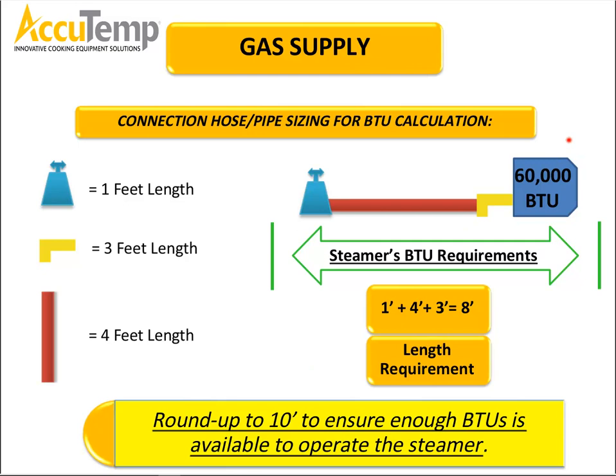Now, one thing to remember is we want to be over by 10%. In other words, if you go bare minimum and say, hey, I can hook this up, and yes, in my calculations I've got exactly 60,000 BTUs running at this connection, nope, add 10% to that. I want to see that connection be able to support 70,000 or 66,000 BTUs. And from that point, we do have that 10% buffer.